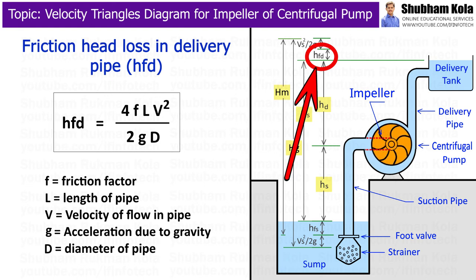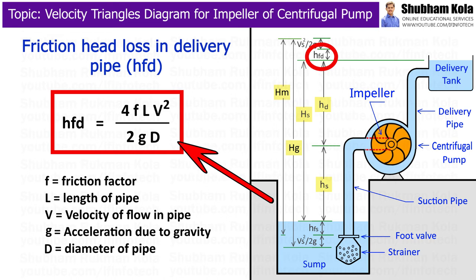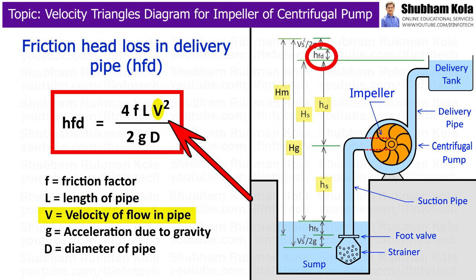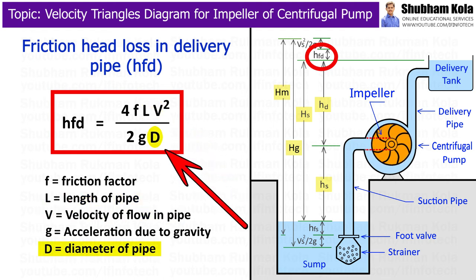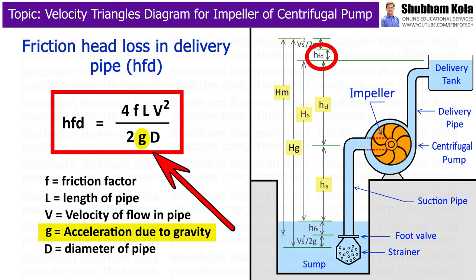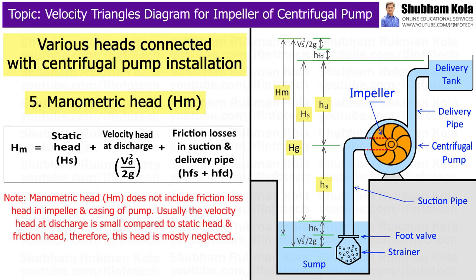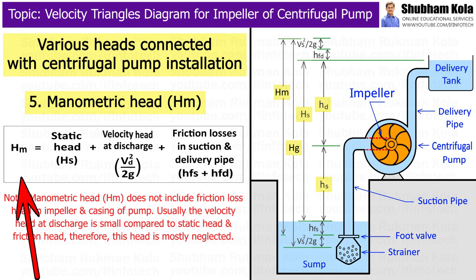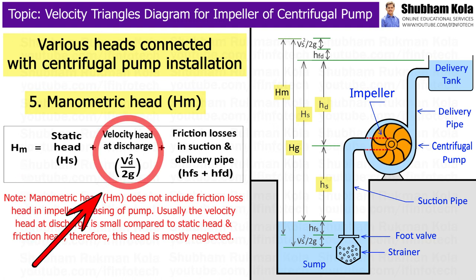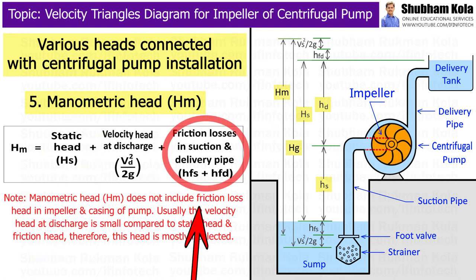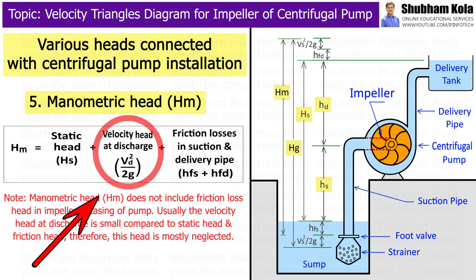The friction head loss in the delivery pipe, HFd, is given by the formula: 4·F·L·V² / (2·g·D), where F is the friction factor, L is the length of pipe, V is the velocity of flow in pipe, D is the diameter of pipe, and g is the acceleration due to gravity. It should be noted that manometric head does not include friction loss in the impeller and casing of the pump. Usually, the velocity head at discharge is small compared to static head and friction head, and is therefore mostly neglected.